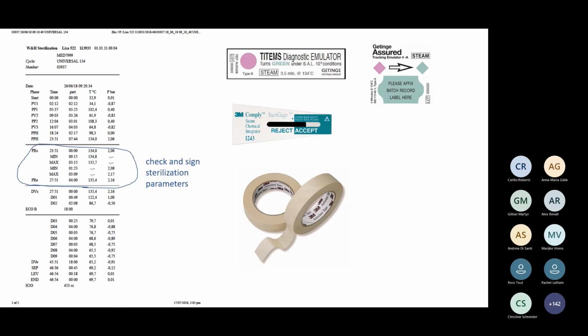So when you're looking at a printout, I've circled that area, and it'll say different things for different machines, but you'll generally see some of them say SS, or this one says PRS, PRE, whatever, but it's the sterilization time. So this machine, you can see it went into sterilization, which is the PRS. It was hit at 134 degrees, and then its holding time was 4 minutes. You can see how it's counted across to 4 minutes. In that 4-minute period, you need to identify the highest temperature. So the highest temperature was 135.7 in that particular load. These are the different types of indicators that you might use in part of your tracking.